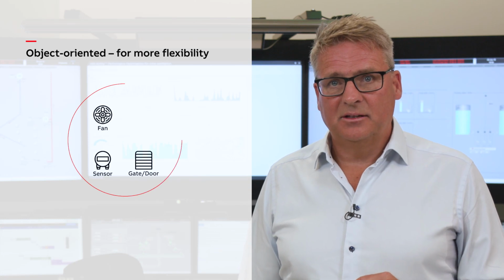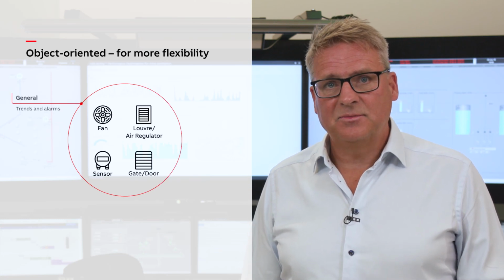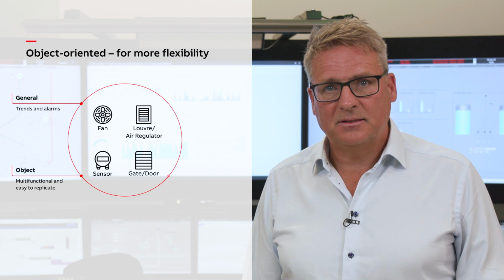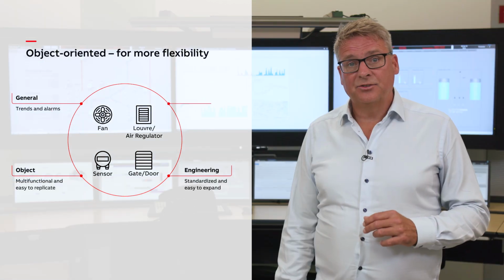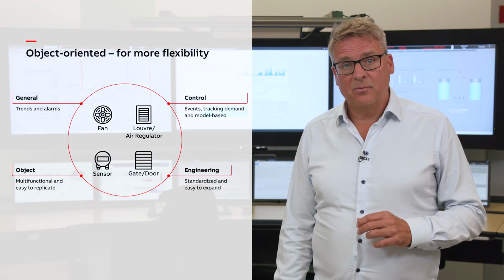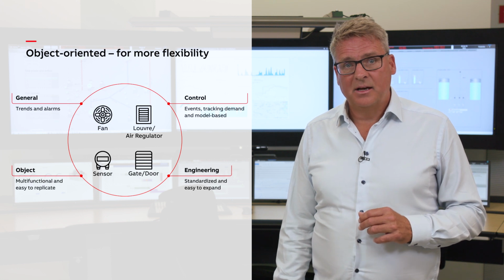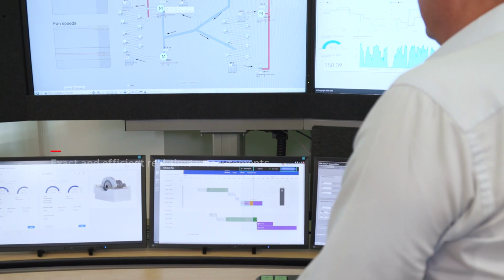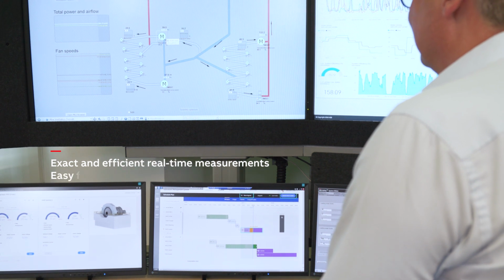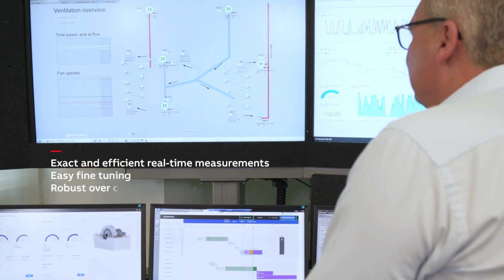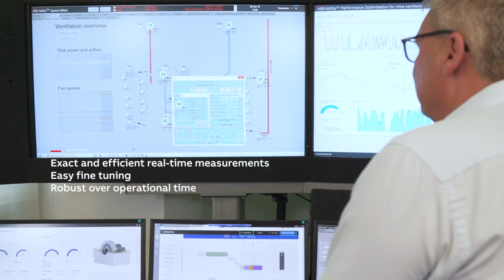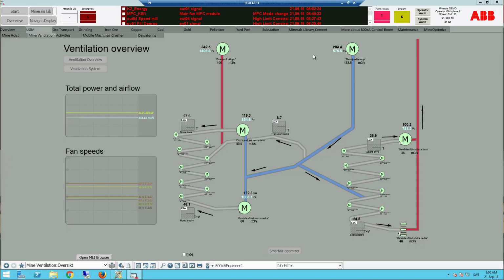With ABB Ability Ventilation Optimizer, a system's need can be scheduled, event-based, or captured in real time with either a tracking tagging system or environmental and flow sensors. Efficient air distribution is achieved with the built-in parent-child object model, or by using an empirical model extracted from real-time data and used in closed feedback loop operation.